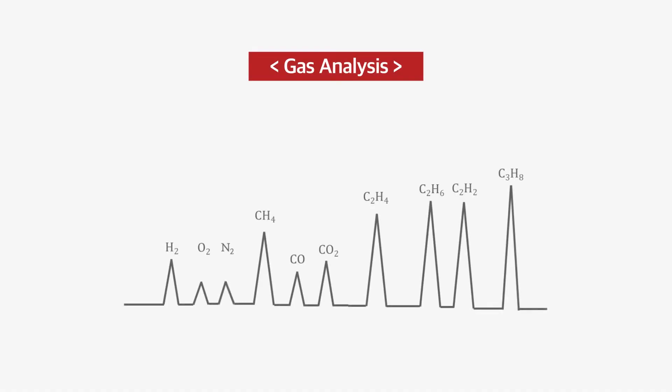Hydrogen to carbon monoxide are separated in molecular sieve column, and carbon dioxide to hydrocarbons over C2 are separated in Porapak N column. Hydrogen and oxygen are detected by TCD. Carbon monoxide and carbon dioxide are transferred to the methanizer to be converted to methane and detected by FID. And the other light hydrocarbons like methane, ethane, ethylene, acetylene, and propane are detected by FID.